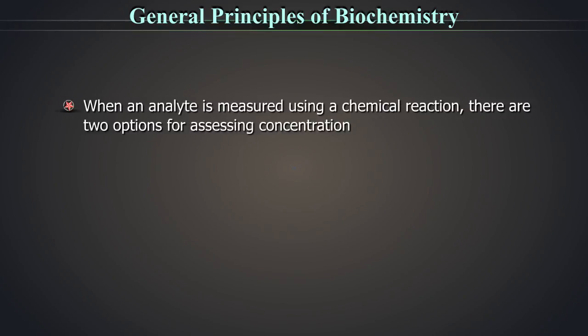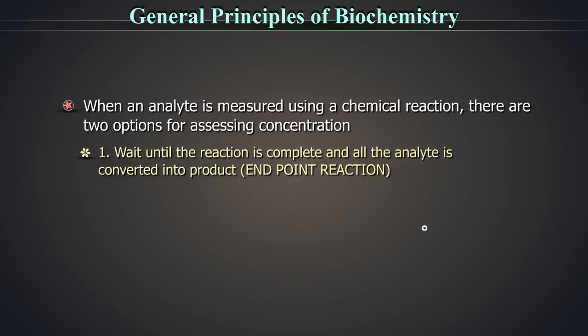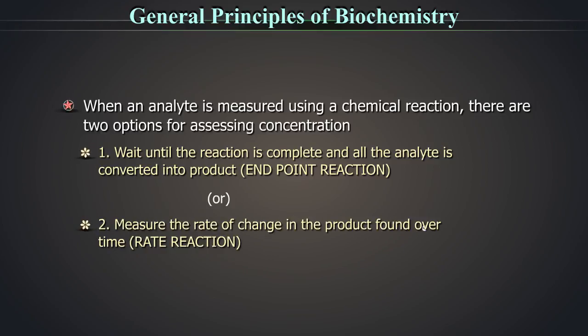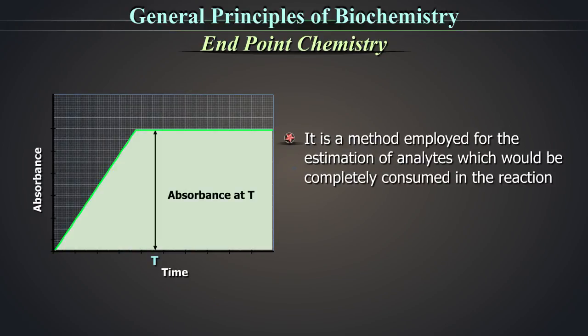When an analyte is measured using a chemical reaction, there are two options for assessing concentration. Wait until the reaction is complete and all of the analyte is converted into the product. This is called endpoint reaction. Or measure the rate of change in the product found over time. This is called rate reaction. Endpoint chemistry: a method employed for the estimation of analytes which would be completely consumed in the reaction. The endpoint for a particular analyte is normally achieved within 5-15 minutes at 37 degrees Celsius.